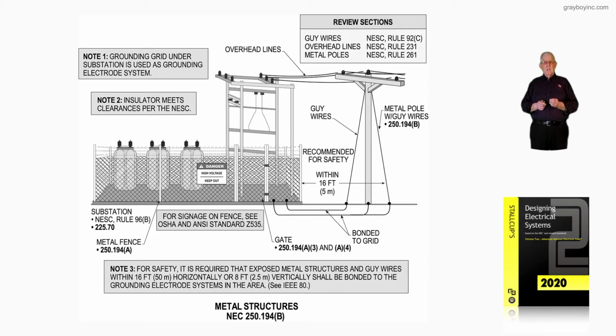Note 3, for safety, it is required that exposed metal structures and guy wires, very important here, within 16 foot horizontally or 8 foot vertically shall be bonded to the grounding electrode system in the area in accordance with IEEE 80. Then the signage, as you see, has to basically have danger, high voltage, or danger, high voltage, authorized personnel only, in accordance with OSHA and the ANSI standard Z535.4. Now, the substations are also discussed grounding-wise in the National Electrical Safety Code, Rule 96B.